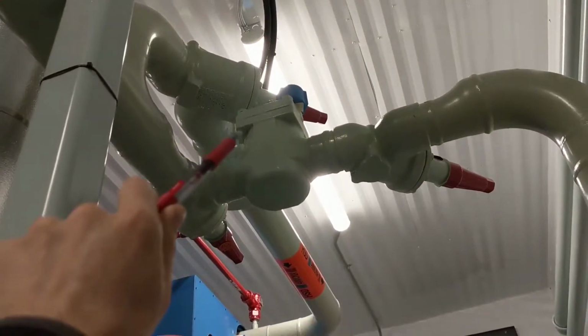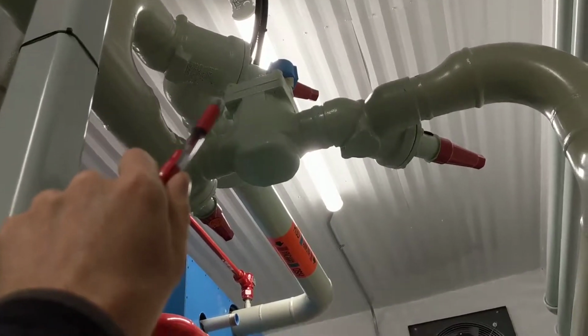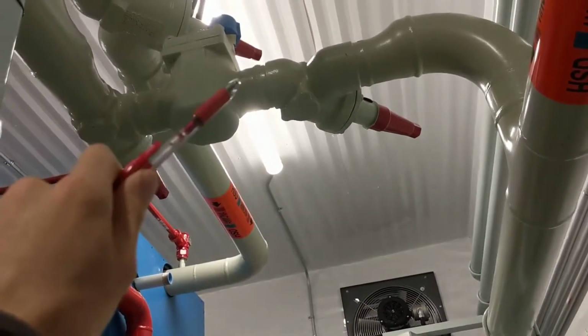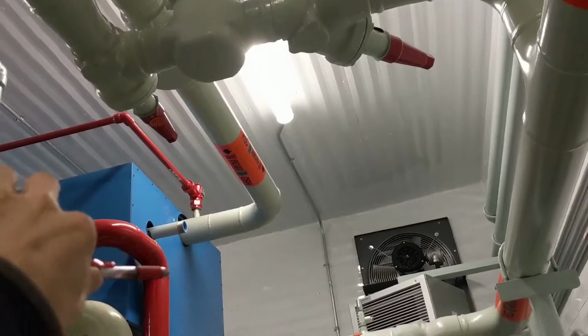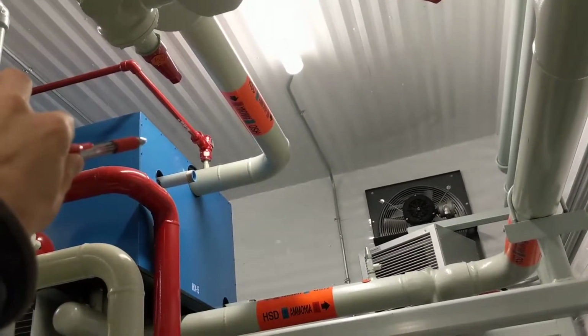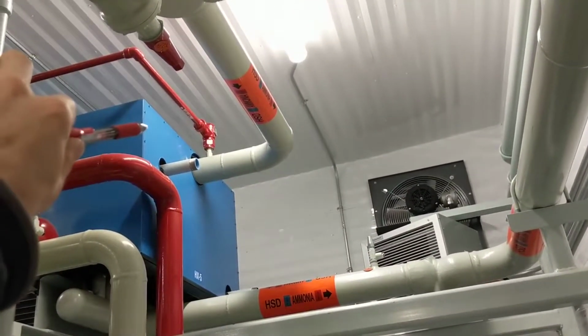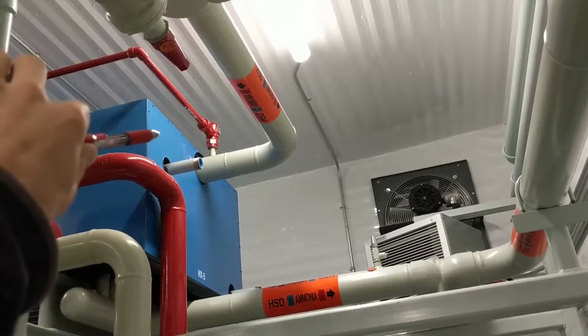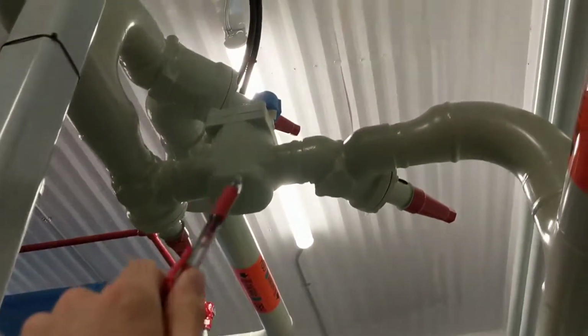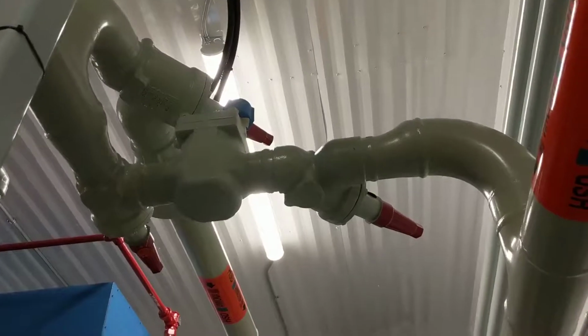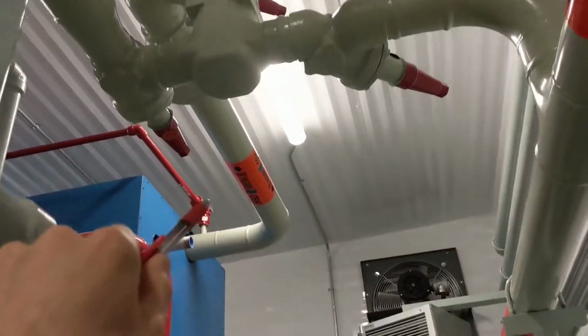This here can control whether the ammonia gets fed to the desuperheater or bypasses it, and that's because if, say, your domestic hot water was already hot enough, you don't want to boil the water, so you need to bypass it and funnel it past the desuperheater instead of through it.